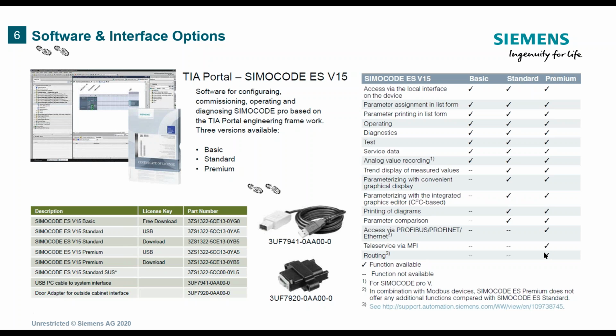He can do some mass engineering, where if he has 6 size 5s or size 2 starters, he can configure one and mass engineer the other 4 or the other 5. He's able to do access with Profinet. He does not require this cable to program it. He can access it via Ethernet. And this routing is a major way of saving time of walking out in the field and going back and forth from your desk, if you have the means to communicate to the PLC from your office.